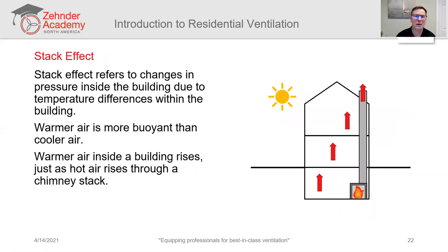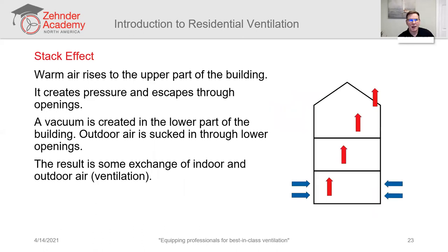Stack effect is maybe not as well understood, although by building professionals probably is. But stack effect refers to changes in pressure inside the building that are due to temperature differences within the building itself. So of course, warmer air is more buoyant than cooler air. And so that warmer air rises up to the upper levels of a building, the same way that smoke rises up a smokestack or whatever vapors are in there.